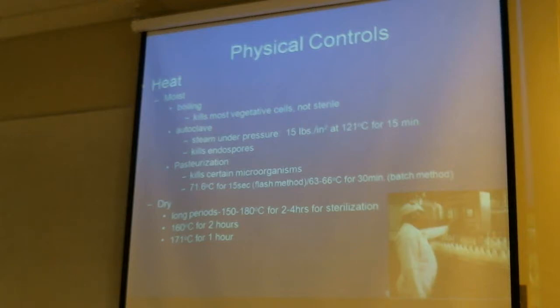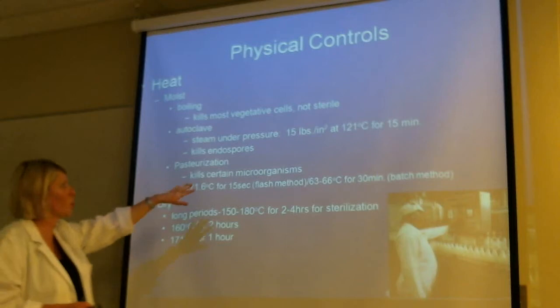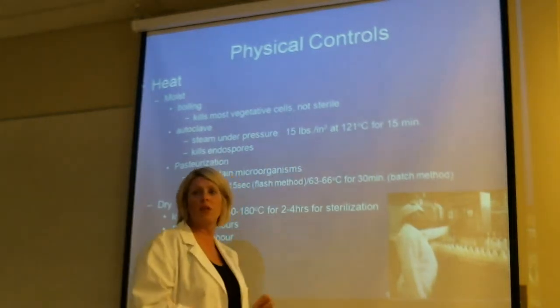The autoclave is good for sterilization, so eliminating spore formers. It's steam under pressure, and if you were to open that autoclave while it was still going, it would make a nice loud whistling sound, and the whole place would fill up with steam. So you could really tell the pressure if you ended up trying to open it. But as far as the requirements, remember it's 121 degrees Celsius for 15 minutes, and it's at 15 psi, that's the pounds per square inch that I have here.